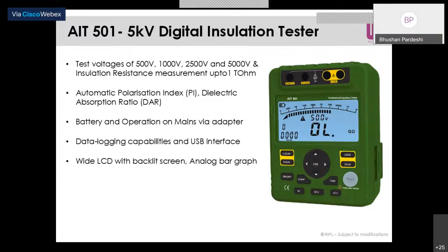What it indicates is that your insulation value should not get degraded from the 1-minute value to the 10-minute value. For example, at 1 minute it's showing 10 kilo ohm, and after 10 minutes if it's showing 5 kilo ohm, that means the insulation is getting degraded. Your molecules are not strong enough to resist the current.